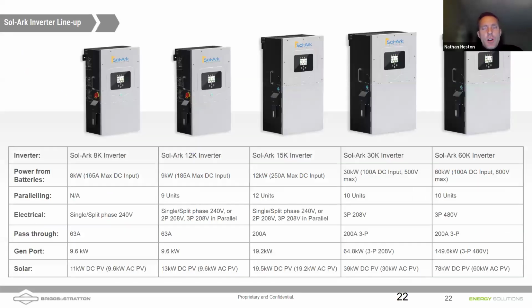Even though this is a talk on whole home, and even though we're featuring mostly the Sol-Ark 15k, I did put together this slide about a year ago just so that you would have the specifications of the full Sol-Ark inverter lineup in a single page. The Sol-Ark 30k and 60k on the right are native 3-phase inverters, so they require a high voltage battery. So you can't use a Sol-Ark 30k with the batteries we're showing on the screen. Briggs & Stratton does make high voltage batteries. The 60k inverter is a native 480. The 30k is a native 208.